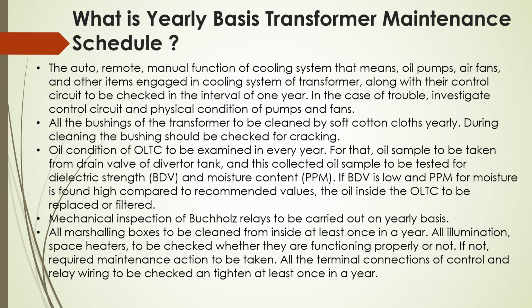What is yearly basis maintenance for the transformer? The auto, remote, manual function of cooling system, that means oil pumps, air fans and other items engaged in the cooling system of transformer along with their control circuit is to be checked in the interval of 1 year. In case of trouble, investigate the control circuit and physical condition of pumps and fan.